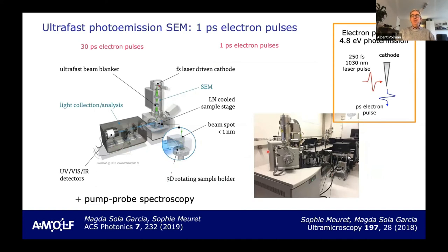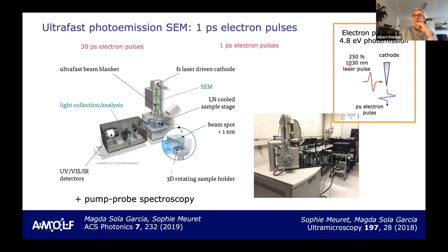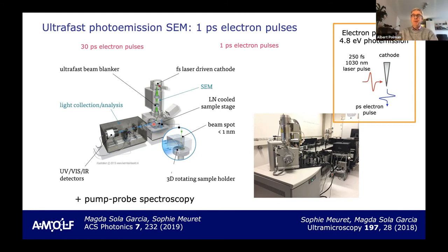I want to show a new microscope we've constructed to bring time resolution down to one picosecond. Here we use photoemission, where a 250 femtosecond laser pulse hits the cathode. We lower the temperature and extraction voltage so it doesn't give a continuous beam. By photoemission we generate a bunch of electrons making picosecond electron pulses. We just published the first paper on this nanoscale spectroscopy, also doing pump-probe spectroscopy: the laser drives the tip to make electron pulses, but the same laser also goes into the sample and optically excites it. We can vary the time delay between the two — pump with the laser and read out with the electron beam or vice versa.